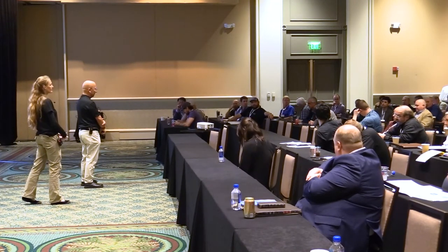Hello. Some of these changes are being addressed by the controls contractor through resubmission, but I'm also seeing owners making changes to an undefined flow meter. We don't want insertion, we want ultrasonic, or there's a sequence of operation that needs to be changed by the engineer. How do you go about getting those significant changes documented aside from commissioning meeting minutes? Are you forcing the architect to issue an ASI or change bulletin? How are you making that part of the contract?